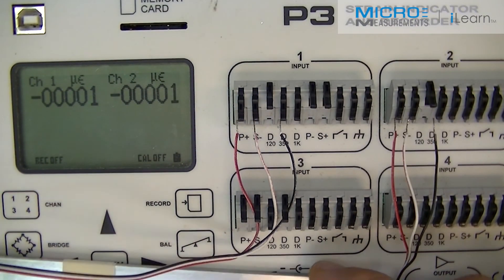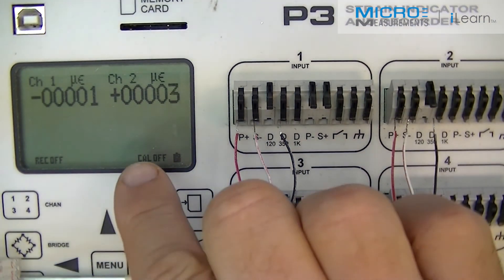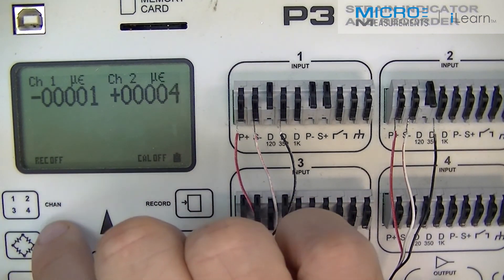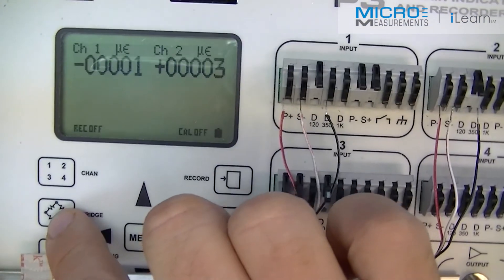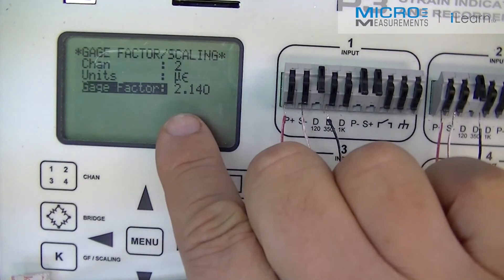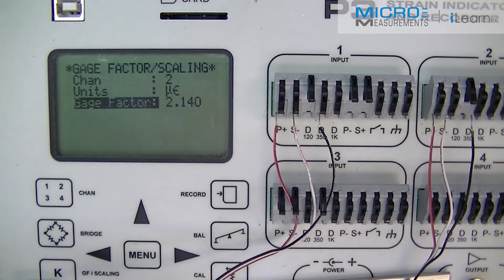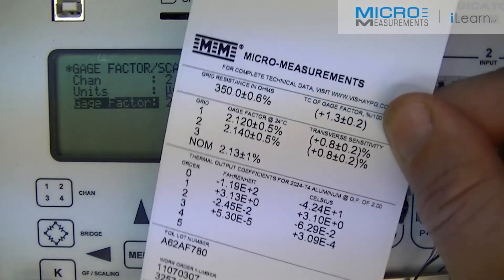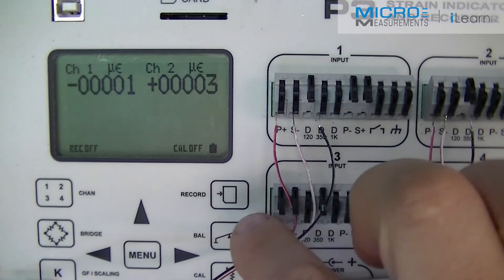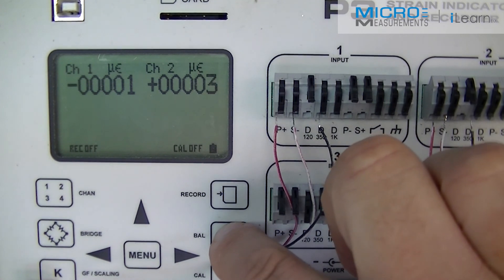Now, what I'm going to do here is I've already set up, I've entered gauge factor, turned on my channel, selected my bridge type for quarter bridge, and I've set gauge factor for grids 1 and 2 to the gauge factor as shown on the engineering data label. With that being done, I'm now ready to zero balance my strain gauge.